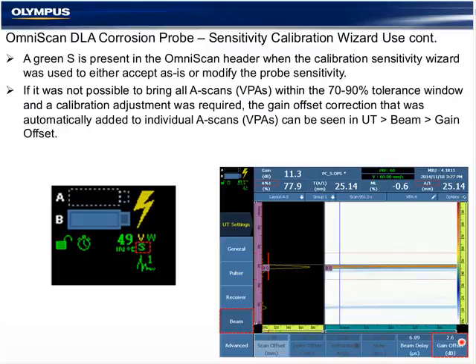If the probe came from the factory and is within the specs on your probe certification sheet and has not been damaged, it would normally not require any calibration for sensitivity. In other words, if your coupling and pressure points are correct across the probe, we should easily be able to maintain the sensitivity of each A-scan on a flat block or reference sample or pipe sample at 70-90% across the whole probe.